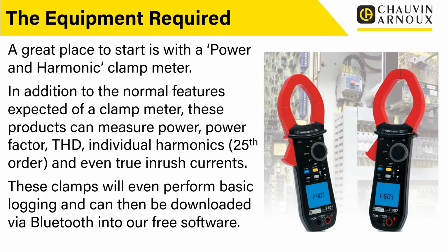And another thing it mentions there, which I just want to go into a bit more detail on, is true inrush currents. What it means by true inrush current is that it actually monitors the current on the circuit, and then when you turn on the piece of equipment you're trying to measure, it measures the additional current, the difference. So it identifies what the steady state of the circuit is. It measures what's going on during the inrush period, and then it identifies the steady state at the end. And it will give you an idea of the inrush of what's going on.